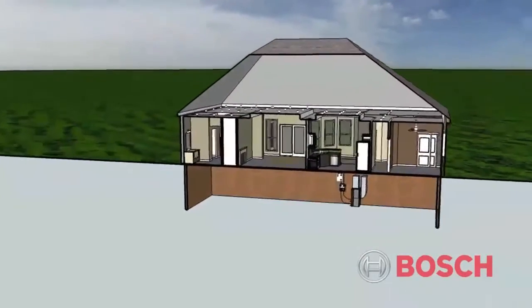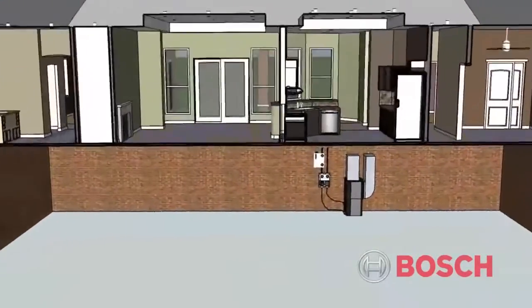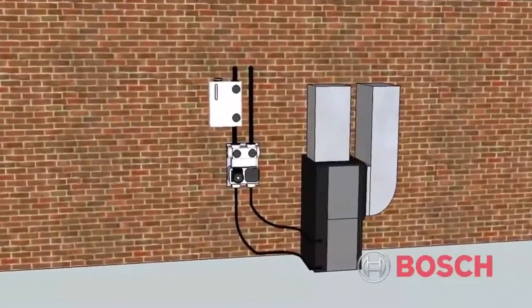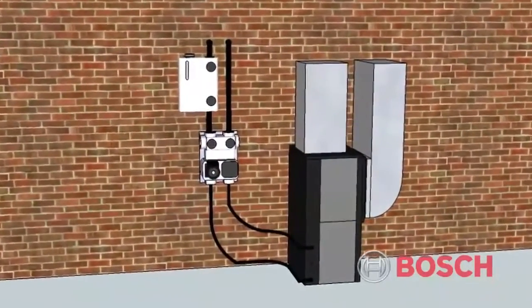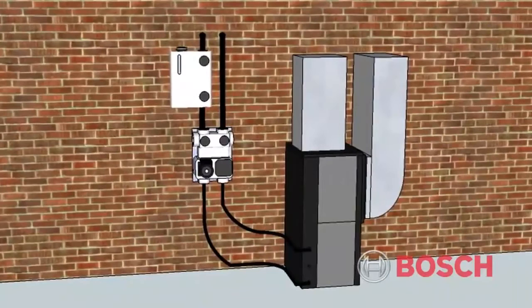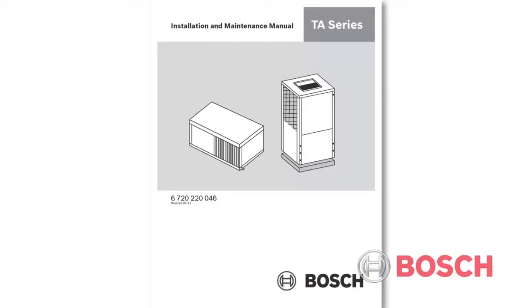In areas where the minimum loop temperatures drop below 42 degrees Fahrenheit, or when the piping will be routed through areas subject to freezing, an antifreeze solution is required. When using an antifreeze solution, we'd have to calculate the freeze protection percentage based on the total volume of fluid. For more details on this process, please reference the installation manual.